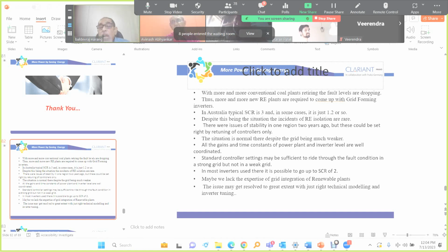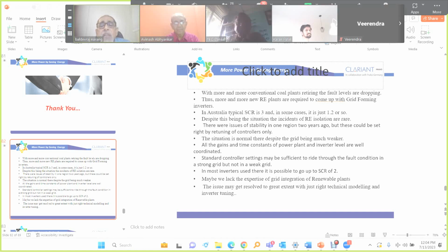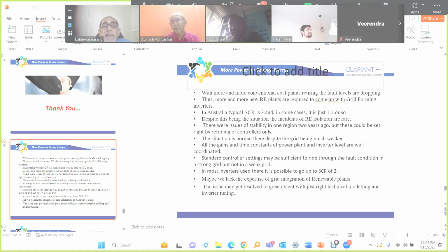What I was saying is that when we have inverters which already have reserve, unused capacity, why are we jumping onto StatComs additionally, increasing the capex unnecessarily? You see, reactive power is decided by the user, not by the generating plant. The generating plant should have the capability, but it doesn't necessarily mean they will supply reactive power, because the demand comes from the voltage control loop. They have to be part of the system, just like conventional plants, which also contribute reactive power as per grid requirements.